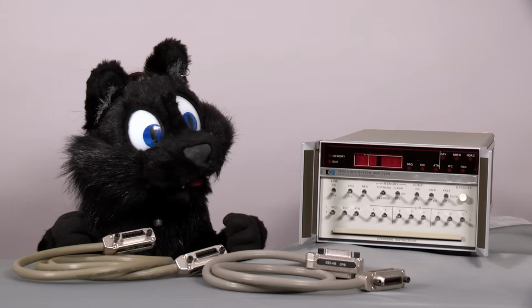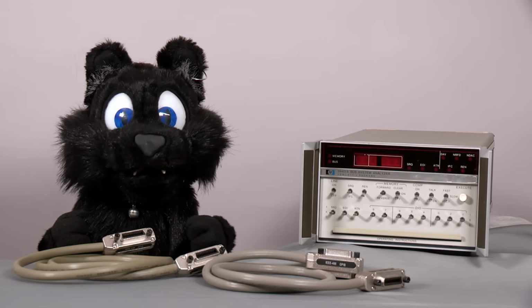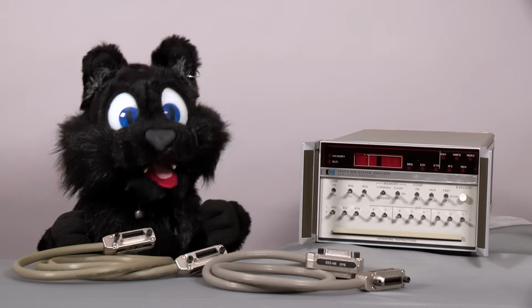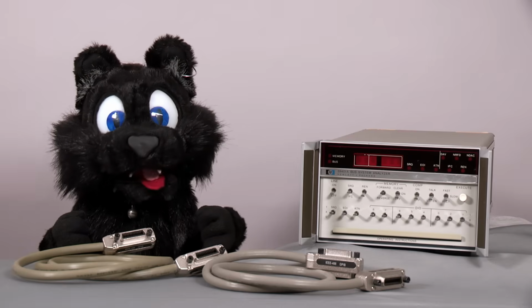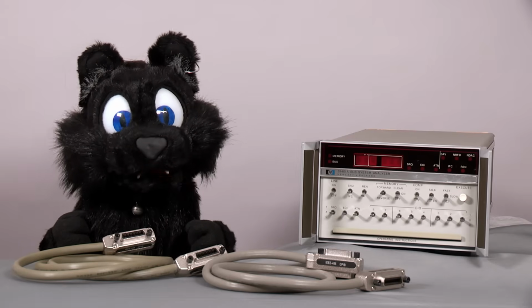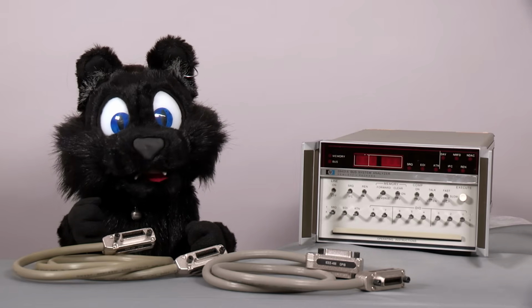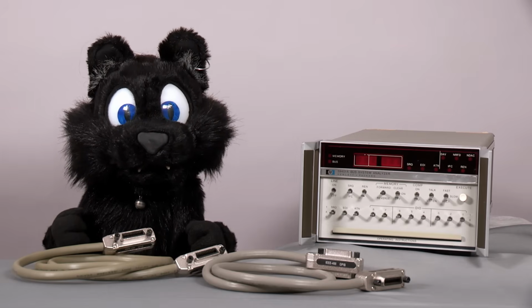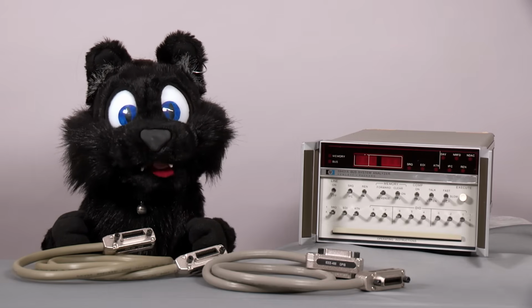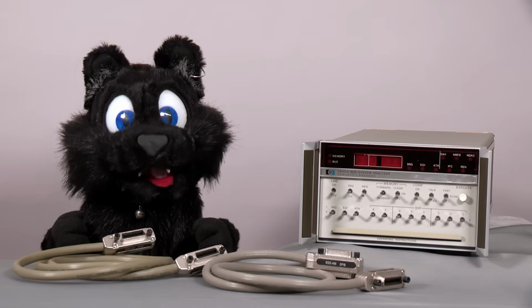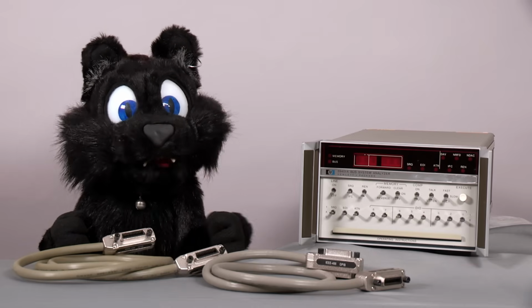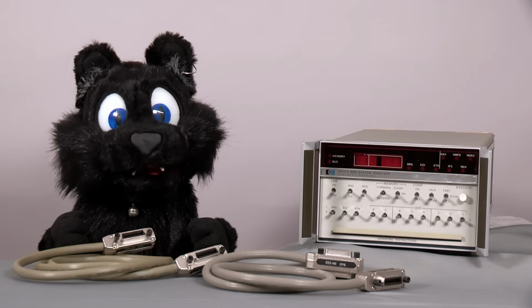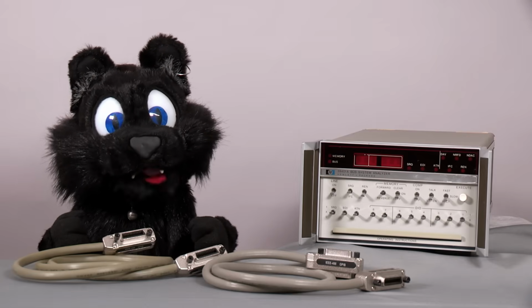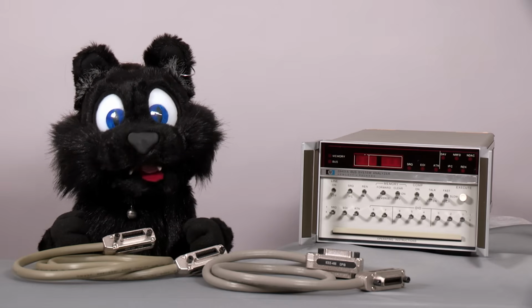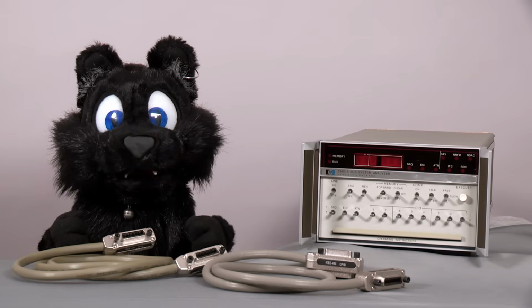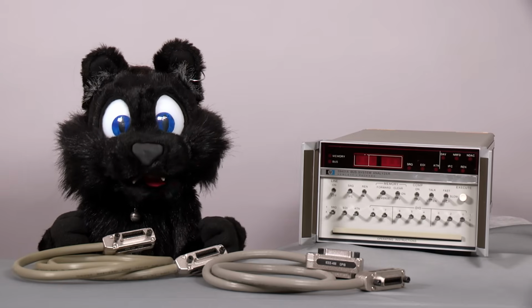Now, what can this thing do? It can listen in on the GPIB bus and store up to, brace yourself, 32 bytes of information from the bus for diagnostics. Or alternatively, you can program a sequence of up to 32 bytes into that same memory and then play it out over the bus. This does limit the application to very low-level diagnostics indeed. Most modern instruments use text-based commands and responses, so 32 bytes is probably at most useful for one command or reply from those. But once the bus interface works, any further diagnostics is better done on the computer anyhow. I still think this will be handy to check up on misbehaving devices on the bus level.